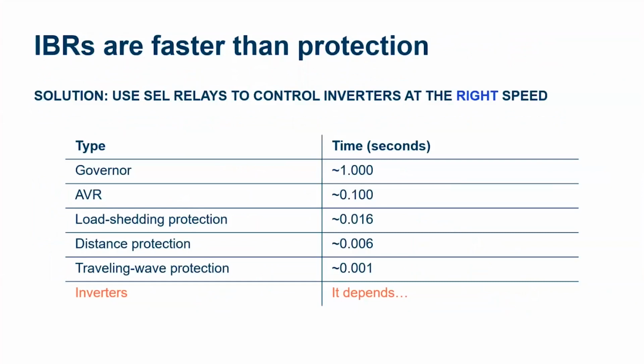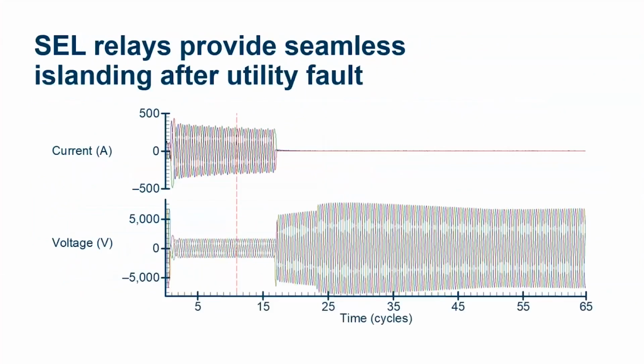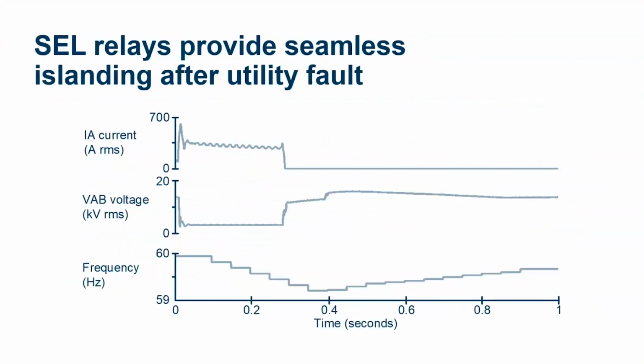Not too fast, not too slow. Stay in line, and all the coordination works. Here's an example of an SEL relay providing seamless islanding after a three-phase bolted utility fault. In this case, you saw a large surge from the subtransient reactance of the generators on this microgrid. They were generators, batteries, and photovoltaics.